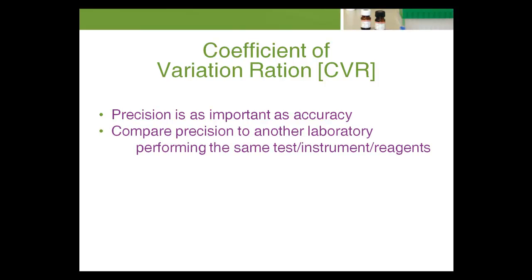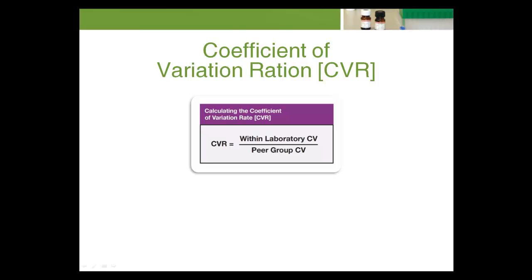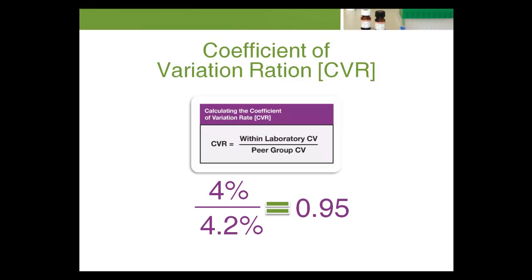Although accuracy of test results is paramount in the clinical laboratory, precision is just as important. One way a laboratory can determine whether the precision of a specific test is acceptable is to compare its precision to that of another laboratory performing the same test on the same instrument using the same reagents. An easy way to make this comparison is to divide the laboratory CV by the laboratory peer group CV obtained from an interlaboratory comparison report. For example, if the CV for potassium on a particular instrument is 4%, and the potassium CV for all other laboratories using the same instrument is 4.2%, then the coefficient of variation ratio (CVR) is 4 over 4.2, or 0.95.